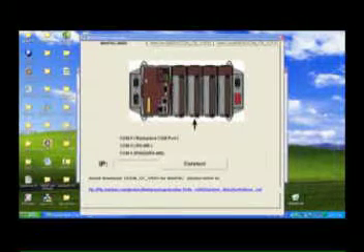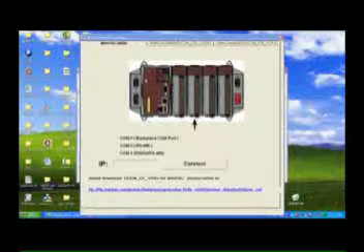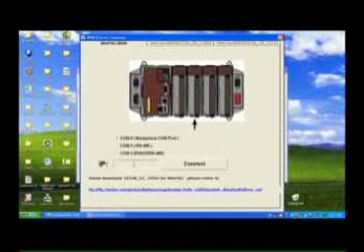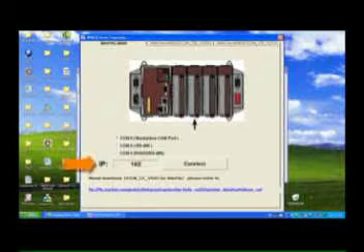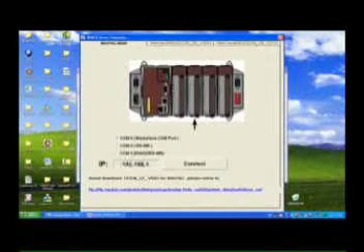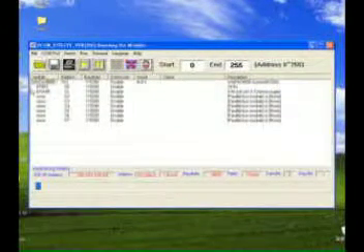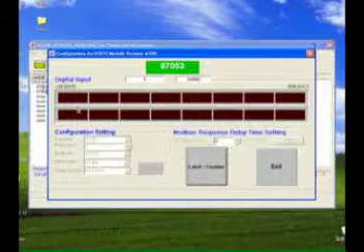After running the program, please click on the top WinCE button. We are going to do some settings here. Because the I-87K modules are assembled on the backplane, we have to choose COM0, which is the backplane COM port, then key in the WinPack's IP address. Click on the Connect button after finishing all the settings. Now our WinPack and all I-87K modules can be scanned by DCON Utility. You can click on the module name shown on this page to set certain I-87K modules.